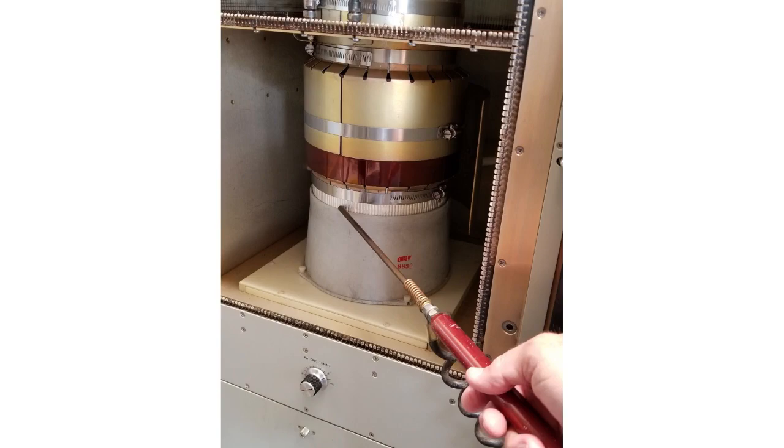It doesn't go through a resistor. It goes straight to ground because it's touching on the side of a 4CX-15000A tube. That tube is putting out around 25 kilowatts. The plate voltage on it runs between 8 and 9 kilovolts. So that's quite a bit of energy. And it runs just under four amps too. So yeah, that's a lot of power going there.